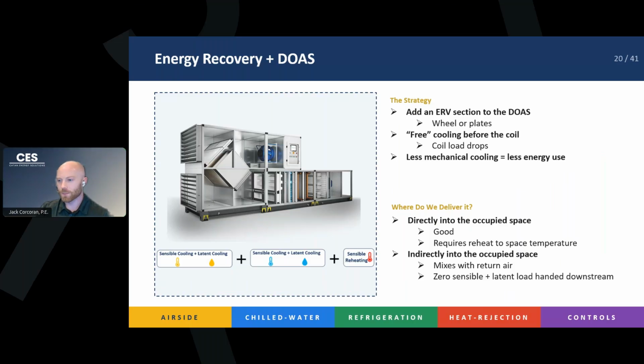So after that, you can pass it over the smaller cooling coil, and then you can do sensible reheating if you need to. This is a very powerful way to cut your energy costs, right? A lot of the times, this is actually required by energy code, or a very powerful way to comply with energy code, because you get that free cooling before you hit the mechanical cooling requirement of the DOAS. So lower energy than a regular DOAS, and you achieve the temperature and humidities that you want at a precise level. And you can deliver this air directly into the room, or you can mix it with a return air in a downstream coil.